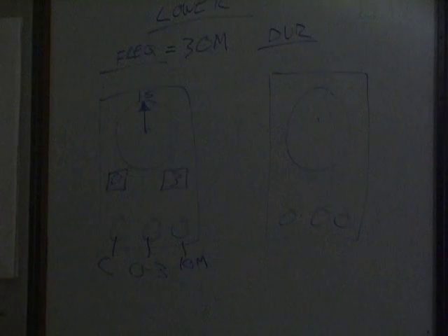We're going to go 1.5. So that's going to get set right at 1.5. So 1.5 times 10 gives you your 15 minutes. That's half of your desired frequency, 30 minutes. So that's going to be the setting for this one.